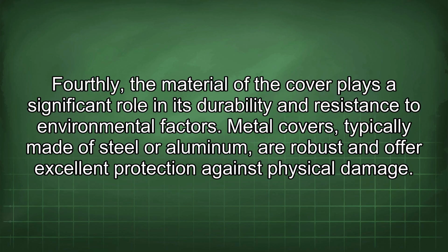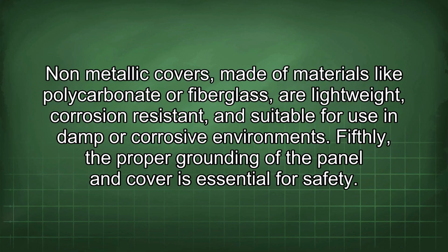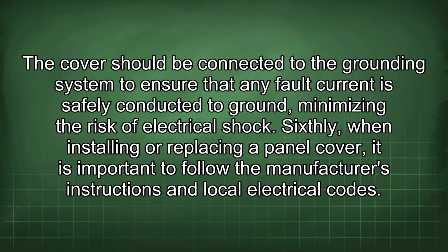Fourthly, the material of the cover plays a significant role in its durability and resistance to environmental factors. Metal covers, typically made of steel or aluminum, are robust and offer excellent protection against physical damage. Non-metallic covers, made of materials like polycarbonate or fiberglass, are lightweight, corrosion-resistant, and suitable for use in damp or corrosive environments. Fifthly, the proper grounding of the panel and cover is essential for safety. The cover should be connected to the grounding system to ensure that any fault current is safely conducted to ground, minimizing the risk of electrical shock.